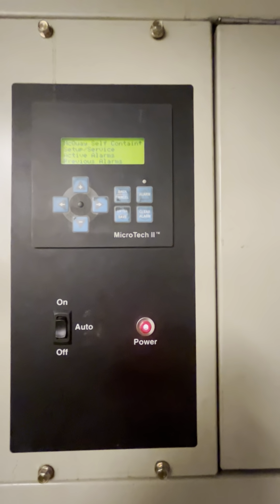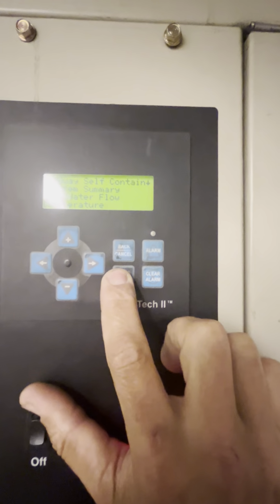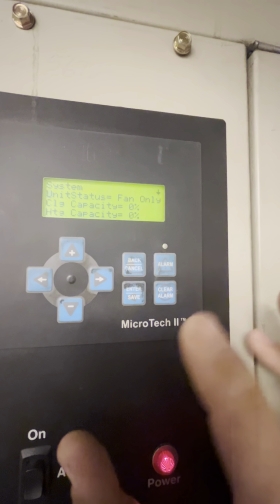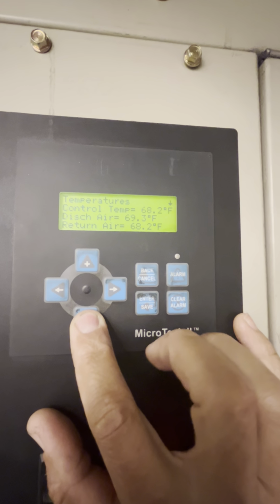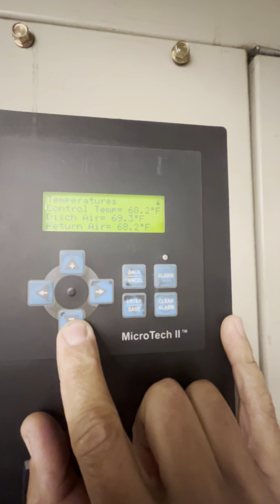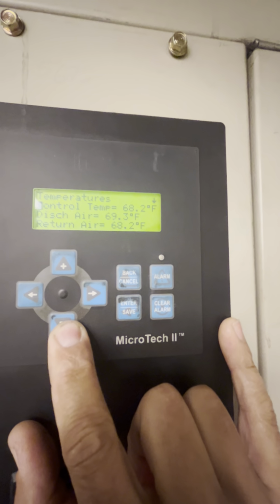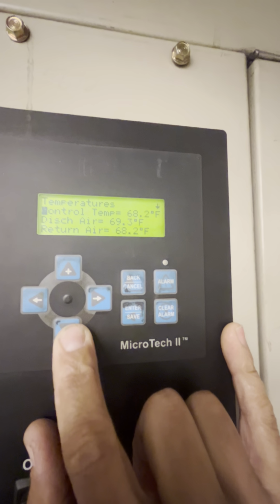This is your Microtech 2 controller. This gives you the basic information about what the unit is doing. We'll go to system summary. Right now it's showing unit status, fan only. If it's cooling, it'll say cooling 25%, 50% based off of how many compressors are running at the time. As we scroll over, we get some important information. Discharge air is the temperature coming out of the unit into the office.